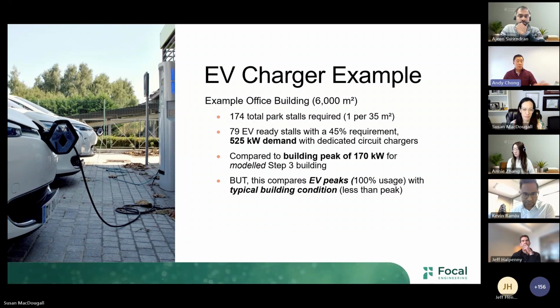A 45% hypothetical would result in just under 80 EV ready stalls. On a very conservative assumption, if that meant a single level 2 charger for each of those stalls, that would equate to a 525 kilowatt demand just for those EVs. Comparing that to the hypothetical modeled office building, the whole rest of the building, heating system, ventilation, HRV fans, lights, plugs, everything else, only comes out to a 170 kilowatt peak, almost exactly a third. So we're at a 3-to-1 ratio from EV charging demand to building peak for everything else, for a modeled step 3 office building.